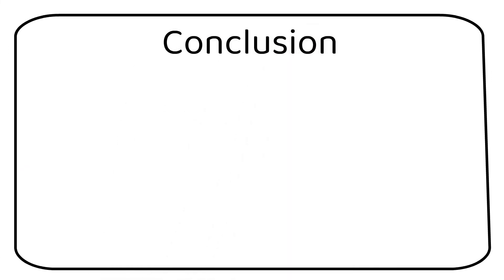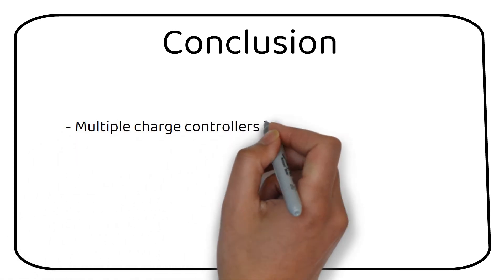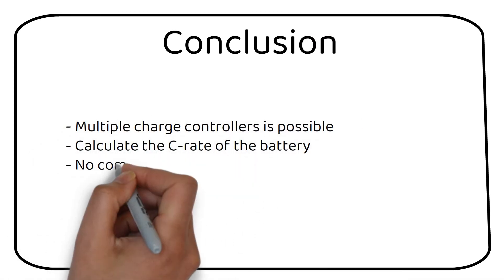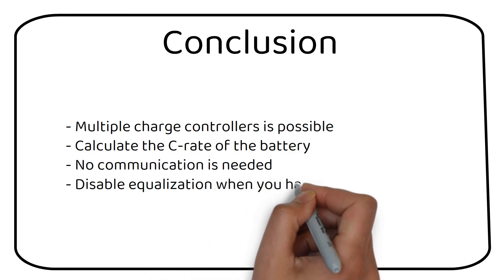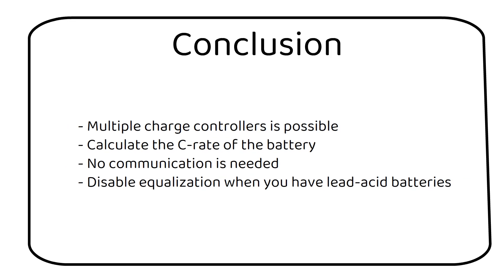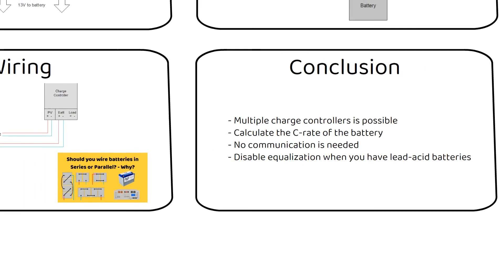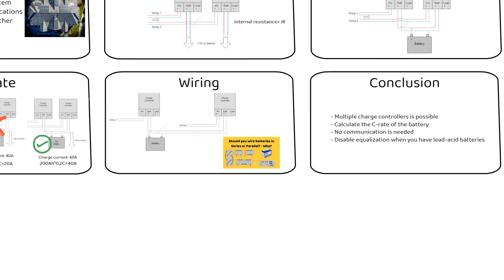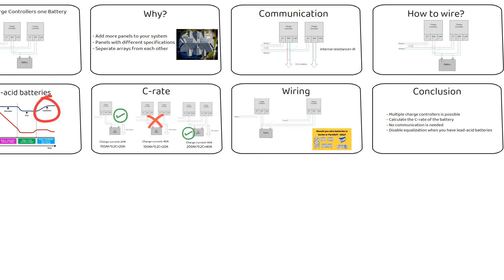You can have multiple charge controllers charging the same battery. Make sure you calculate the C-rate of the battery. Charge controllers do not need to be able to communicate with each other. If you have lead-acid only enable equalization on one of them.